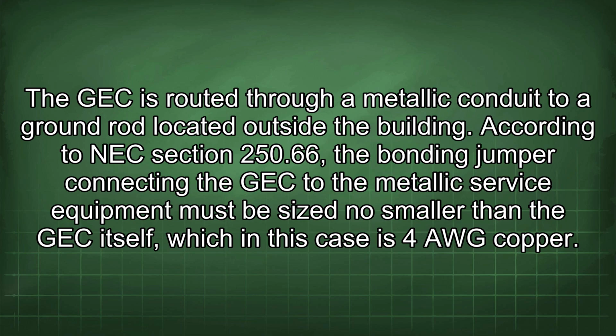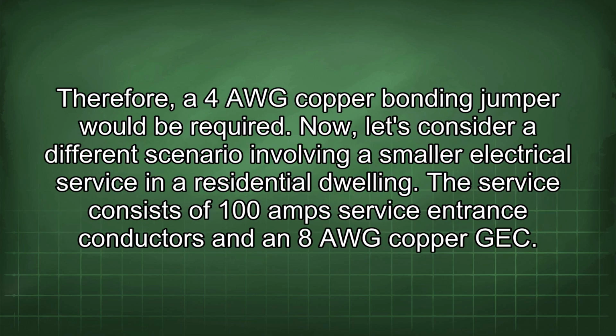According to NEC section 250.66, the bonding jumper connecting the GEC to the metallic service equipment must be sized no smaller than the GEC itself, which in this case is 4 AWG copper. Therefore, a 4 AWG copper bonding jumper would be required.